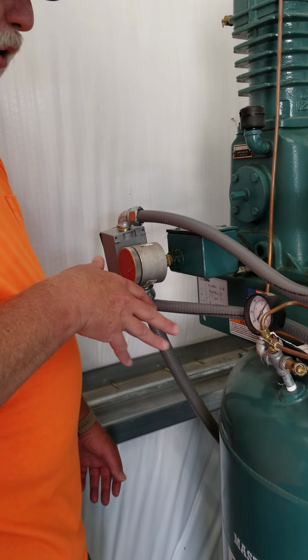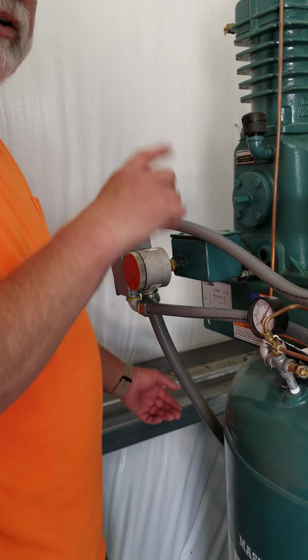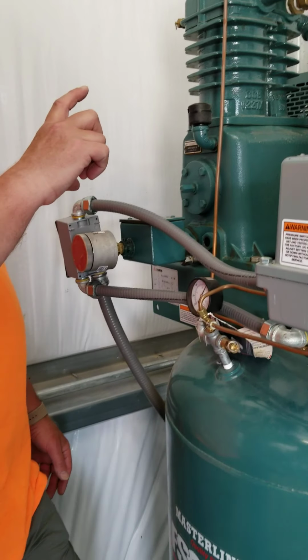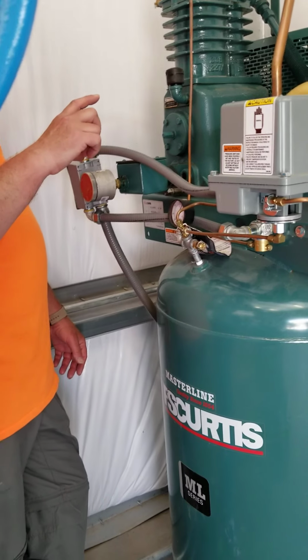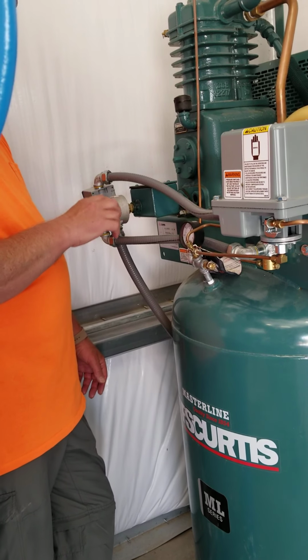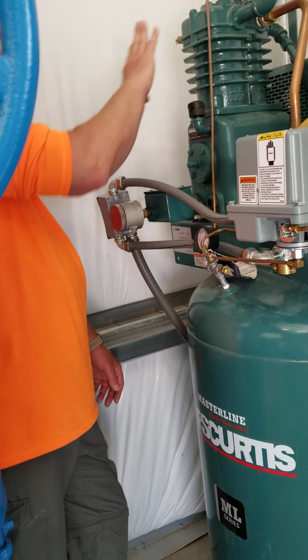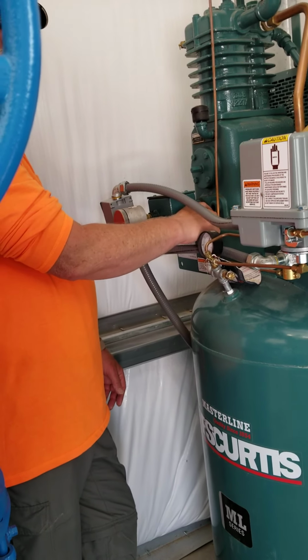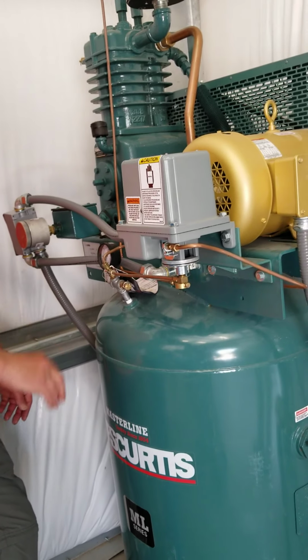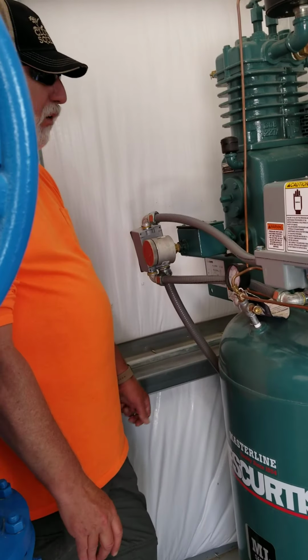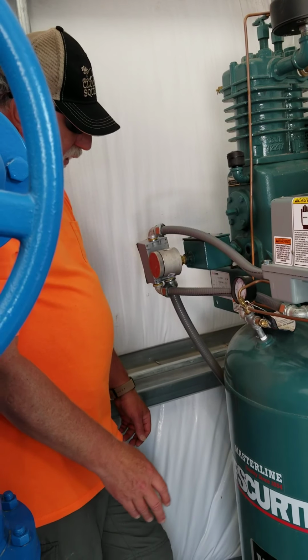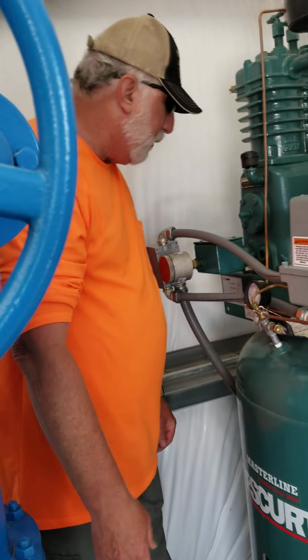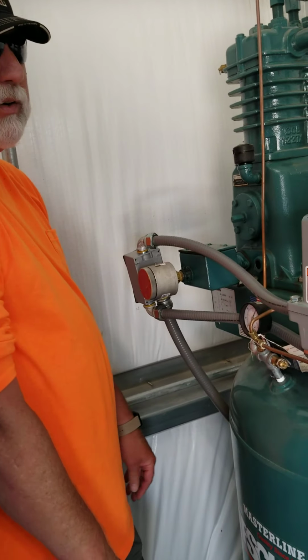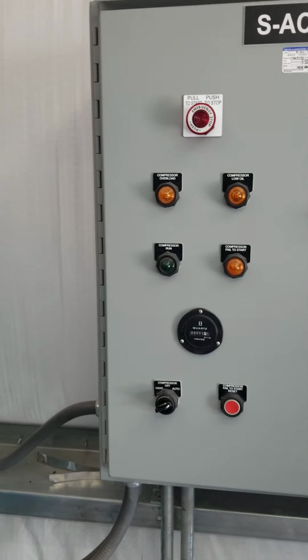You shouldn't have too much of a problem with this on your system because you have a fairly wide gap between the add air and stop add air. But if these compressors don't run for long lengths of time, they can condensate inside the heads, which will drip down into the oil. If the oil starts to get cloudy or foamy, then it needs to be replaced immediately. That is one thing that will void the warranty on these. This first break-in oil should be changed after about the first month, and then you can go by the O&M manual. There's an hour meter on the control panel, which will tell you how many hours are on each unit, so that you can base your maintenance on that.